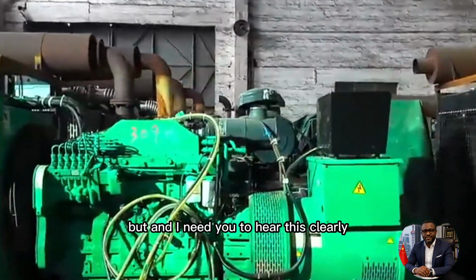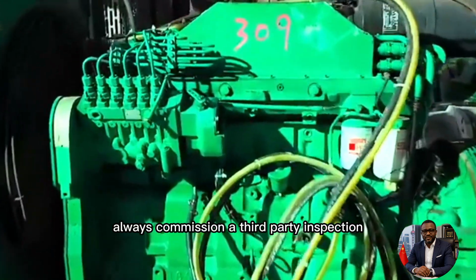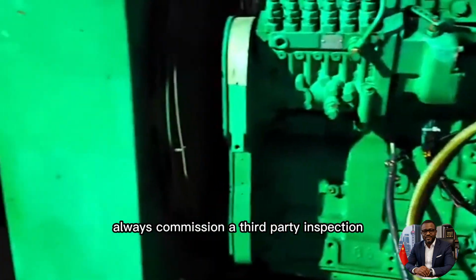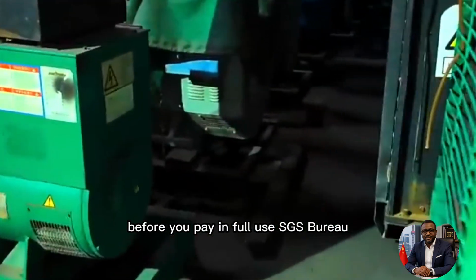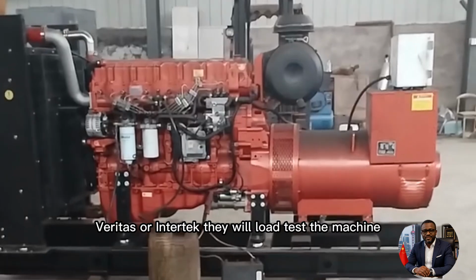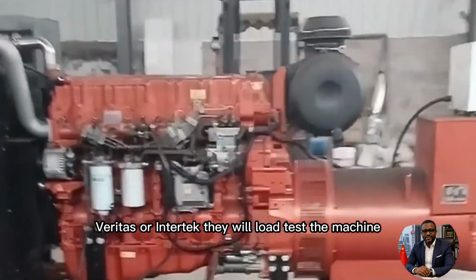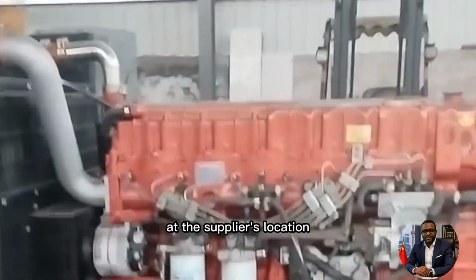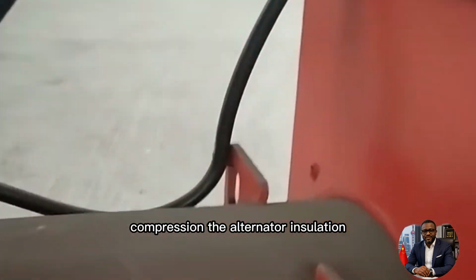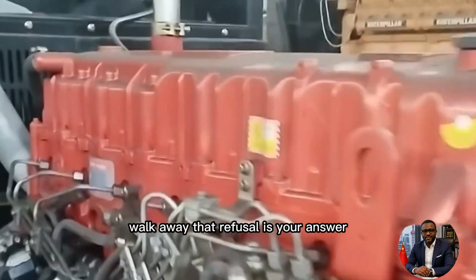But, and I need you to hear this clearly, always commission a third-party inspection before you pay in full. Use SGS, Bureau Veritas, or Intertek. They will load test the machine at the supplier's location. They will check engine hours, compression, the alternator insulation, the control panel. If the supplier refuses inspection, walk away. That refusal is your answer.